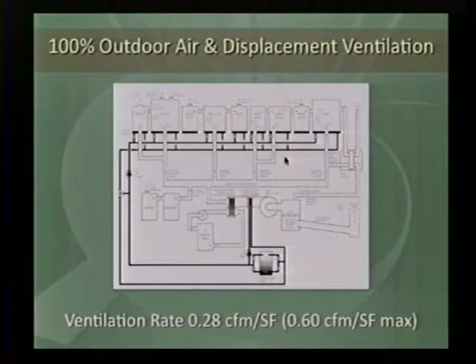So we put the parasitic power in, but all of you know anytime you're doing something new in design, you always miss something. We have a UV lamp, along with a metal filter that is painted with a titanium dioxide coating, to basically respond to anything in terms of bacteria or fungus that may generate in this moist environment. And that UV filter was what we decided on doing. Well, once we actually specified it and it came in, lo and behold, it's 300 watts, and they said, no, you want to run this all the time. You don't want to turn it on and off. Well, that 300 watts probably overcame whatever we were saving in the fan horsepower. So you do learn along the way, and when you're doing new design, there are lessons that you learn both as you make good design decisions and beyond.